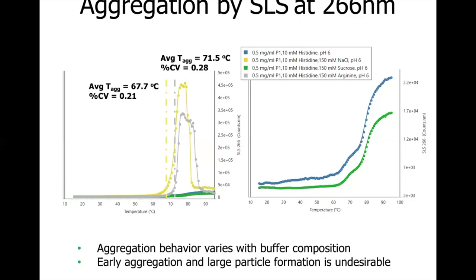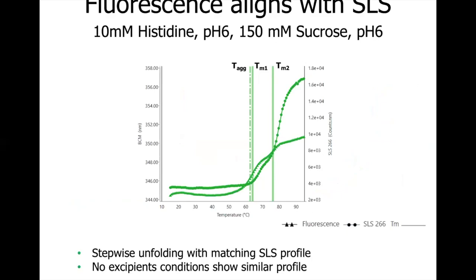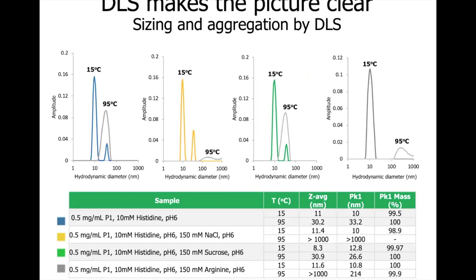Comparatively, there is only a small increase in SLS for sucrose and buffer with no additive, indicating smaller particle formation. The SLS profiles of both buffer conditions show stepwise increases in SLS 266 intensity throughout the temperature ramp. The power of UNCLE is that it collects fluorescence and SLS data simultaneously, allowing for correlation of unfolding and aggregation events. Here is an overlay of fluorescence and SLS thermal profiles for sucrose-containing buffer. We observe a two-step unfolding event with TM1 at 62.2°C and TM2 at 76.1°C, and the SLS profile matches that of fluorescence. The DLS data was collected before and after the thermal ramp — this is optional and user-defined.